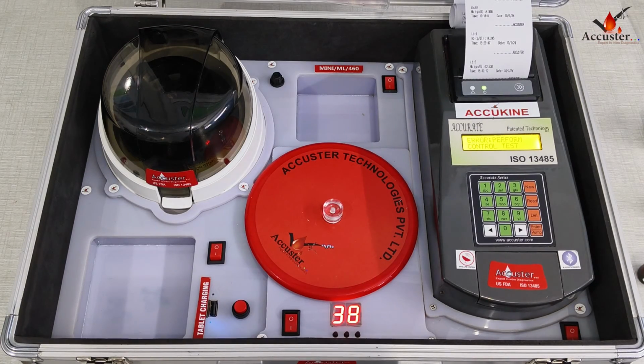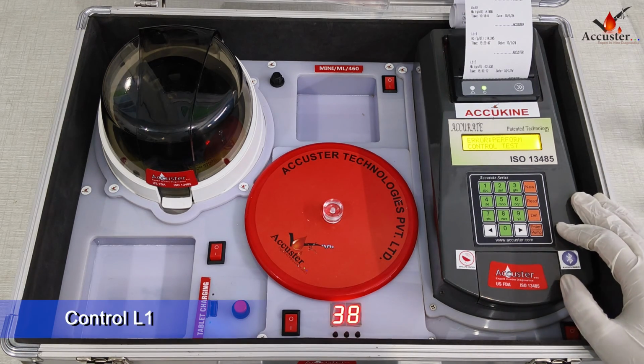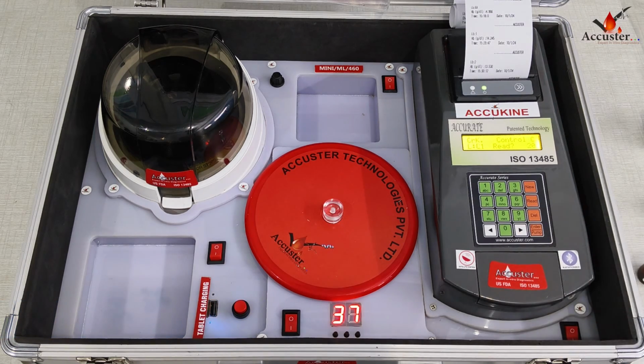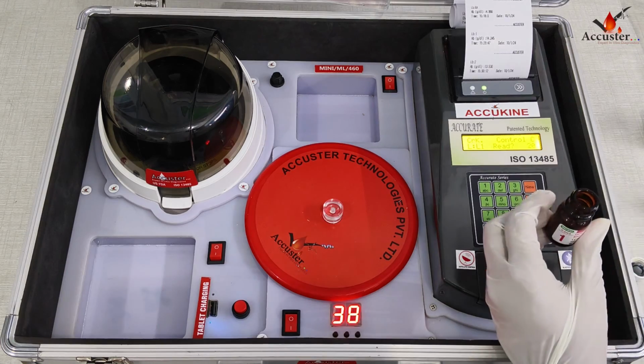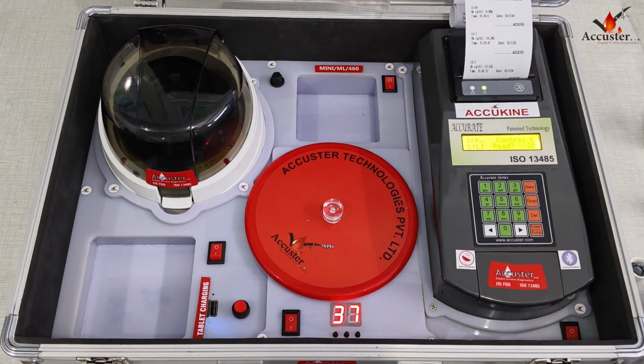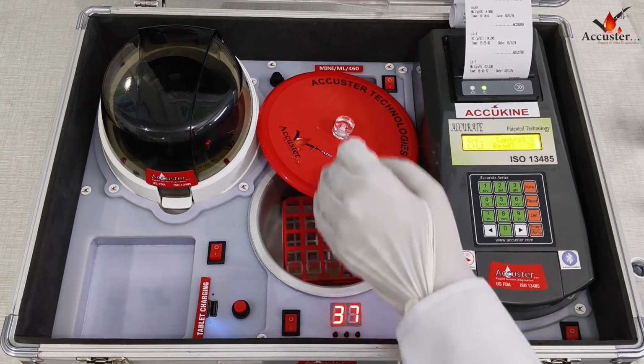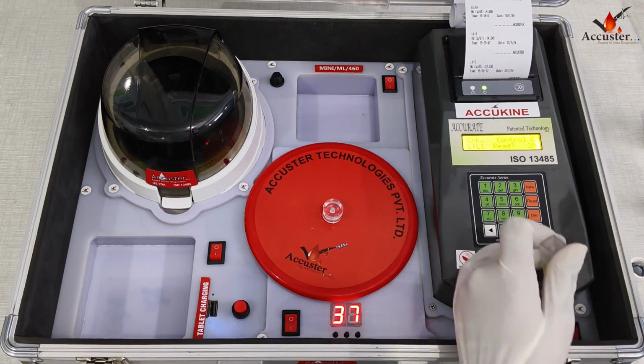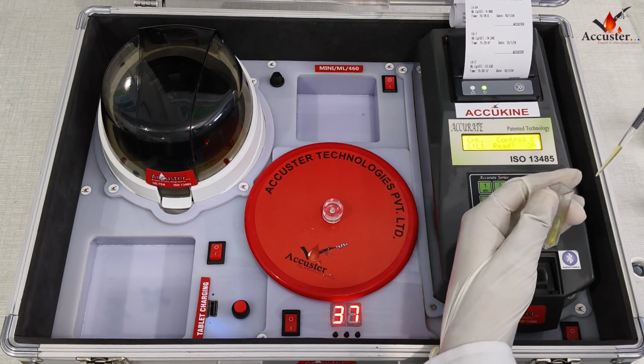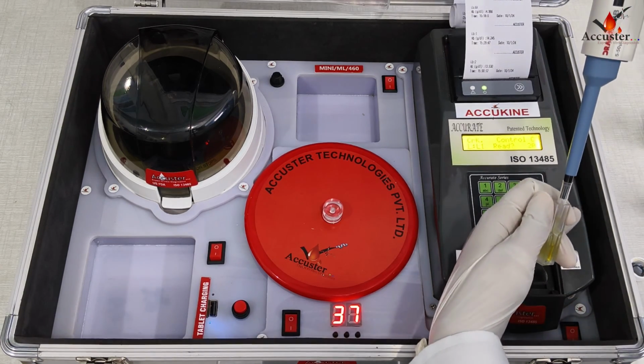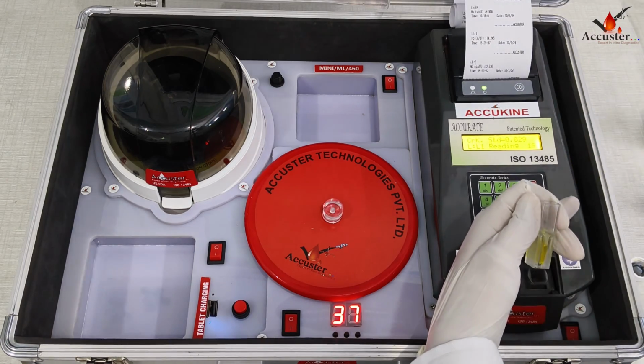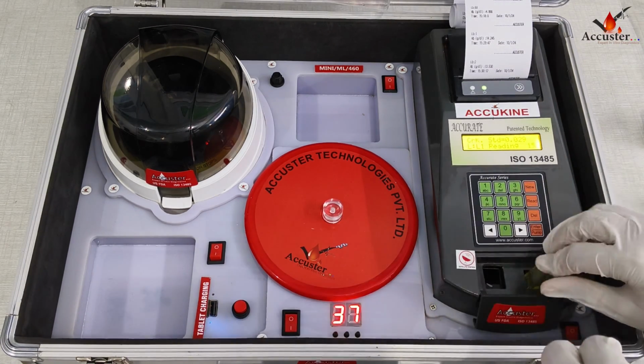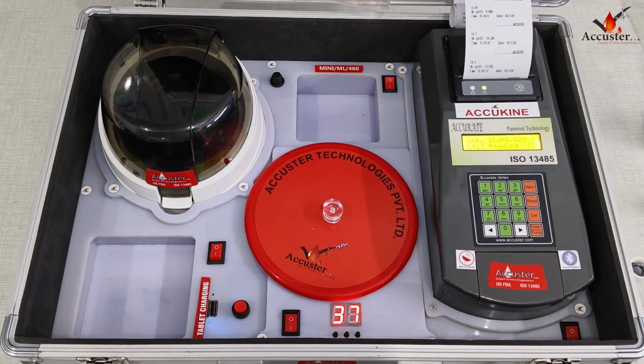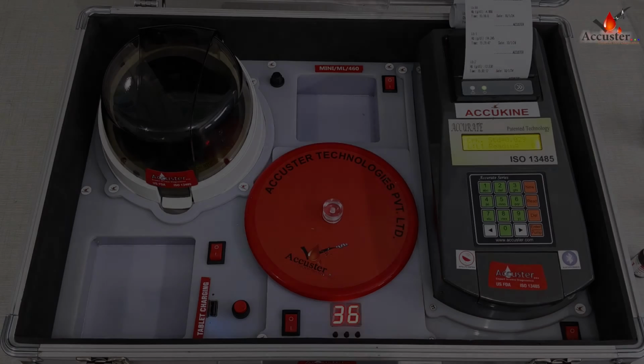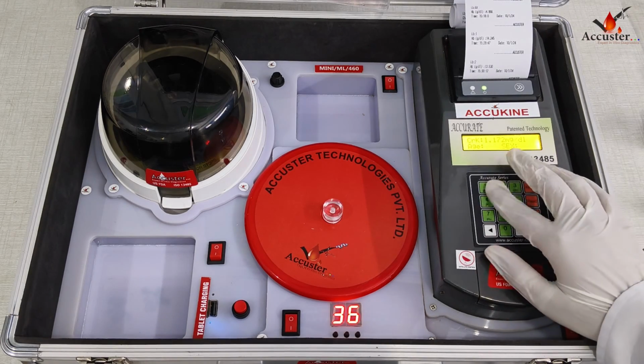Now that the standard concentration is set, proceed to run control, that is L1, and for this press enter and then right arrow to select L1. Then take the other cuvette containing the reagent from the incubator and mix 50 microliters of L1 with the help of a micropipette. Press enter button while mixing the standard. Then insert the cuvettes into the analyzer. The reading will take 80 seconds to display. L1 control has been successfully completed.